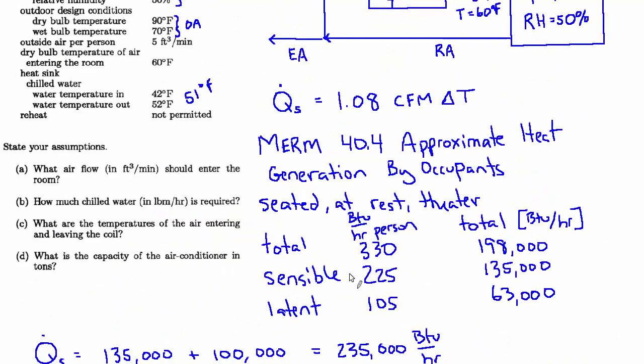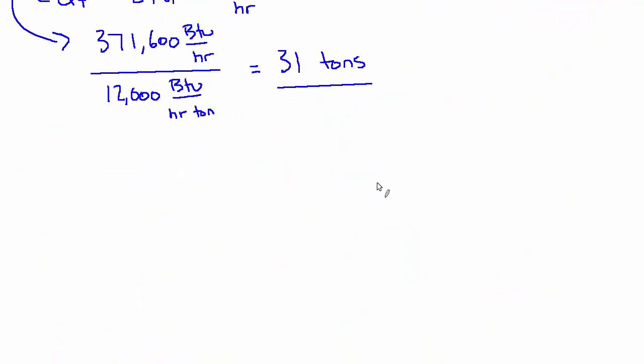The last one we want to know is how much chilled water in pounds per hour. So another rule of thumb, now for the water side, we talked about Q sensible equals 1.08 CFM delta T. That's a rule of thumb we use over and over again. Another one that's extremely common on the water side is the heat load equals 500 GPM delta T.